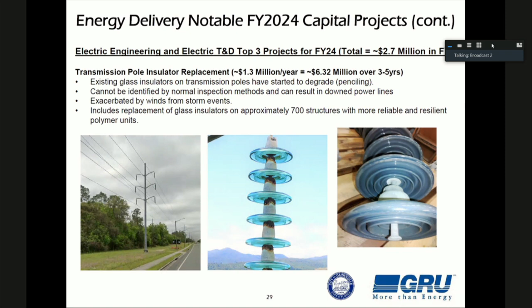As shown in the middle picture, that's a porcelain strain insulator, made of individual insulators held together by a steel pin. Over time, depending on the environment, heat and cold cause corrosion that makes that pin fail. If you wait long enough, you can end up with a transmission line on the ground, which is why it's critical to get these transmission line insulators replaced. The total cost of that project is $6.3 million over 3 to 5 years, about a little over $1 million per year.